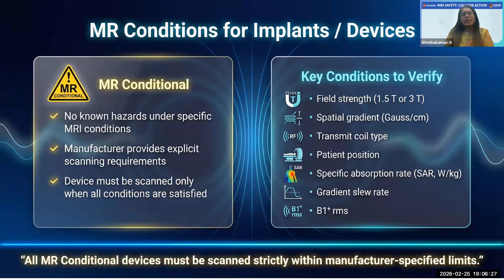So the condition regarding the static field means that it will be specified as conditional up to 1.5 Tesla, up to 3 Tesla, or 3T only. A device which is conditional up to 3 Tesla means we can scan at either 1.5 Tesla or 3 Tesla, or a lower system. But once it is specified as 3 Tesla only, we should not scan at lower Tesla, because we know that resonant heating doesn't scale with the field strength. So being conditional at a higher Tesla doesn't guarantee its safety at a lower Tesla.